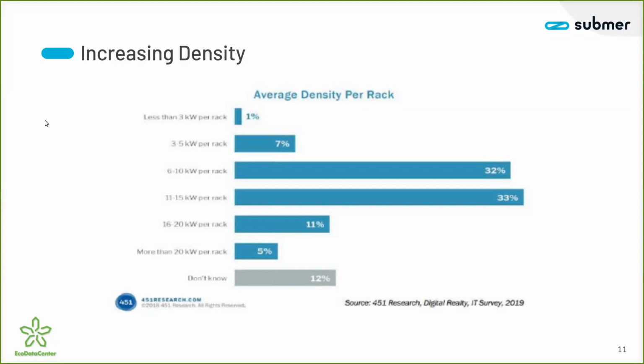That could still be supported by air cooling, but if you go up more than 20 to 25 kilowatts per rack, I would be more careful in providing that kind of service. I would rather go for a suggested liquid cooling solution, which is different from air cooling. That's what we are focusing on at EcoDataCenter.